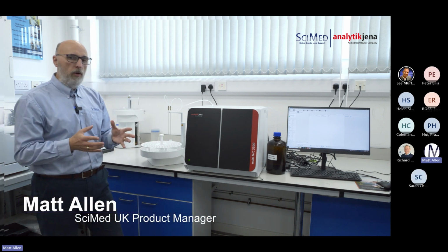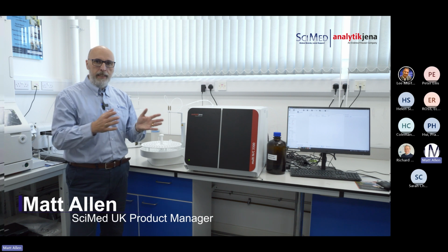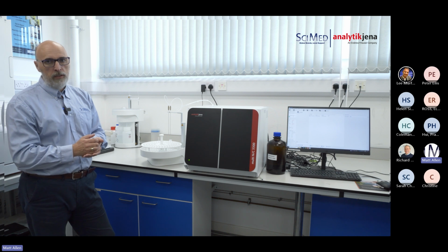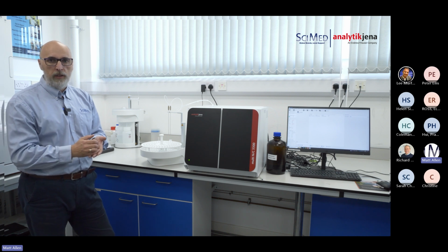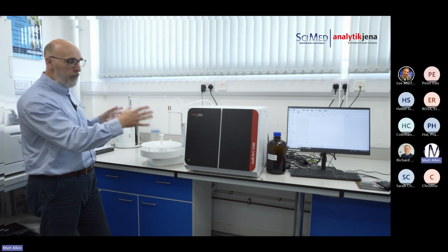Now let's have a quick look at the hardware. There are three systems in the Analytik Jena family of multi N/C units. The 2300 is a direct injection mechanism, but uses a high temperature combustion furnace. The 3300 is a flow injection system, again high temperature combustion. And the 4300 is again flow injection, but uses a UV cell to do the combustion. This system here is our demonstration model. We've had it for a couple of months, and as you can see, this is the NC3300.